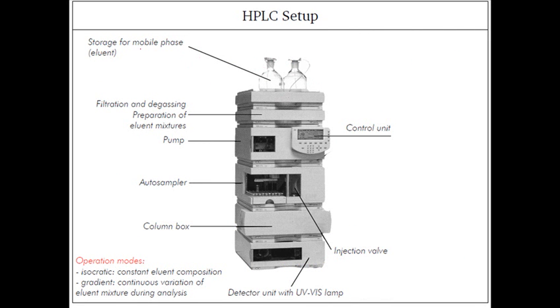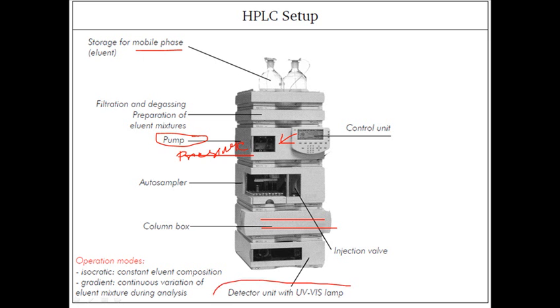In the HPLC setup, we have a reservoir for storing the mobile phase, followed by filtration and preparation. The pump generates the pressure, and a control unit regulates how much pressure is needed to transfer the mobile phase through the column. An auto-sampler loads the sample in small parts into the column via six-port injection ports. The column is placed in a column box where temperature is regulated — an optimum temperature is needed because ionic, polar, and non-polar interactions are all temperature-dependent. A UV-visible lamp detector is also present.